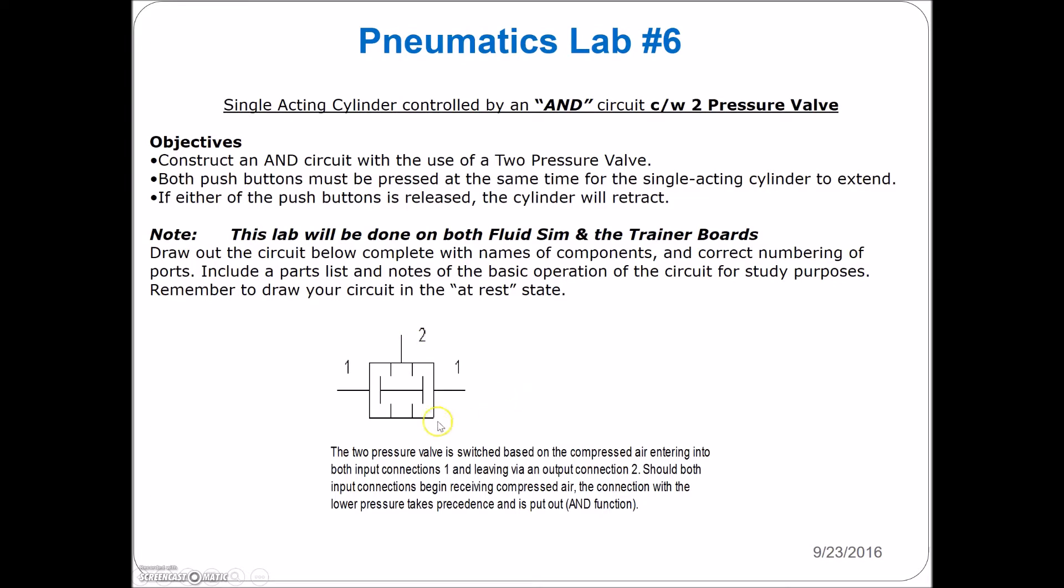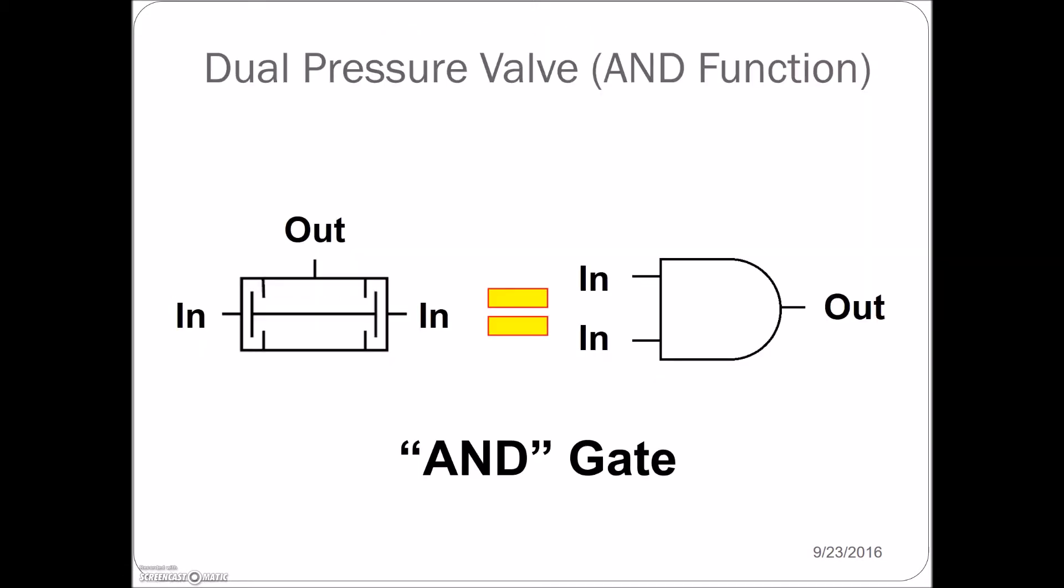The way that you'll distinguish which one this is in the lab is embossed on the front—it'll have this exact image of the AND valve. The other name for this is the two-pressure valve, which needs two pressures of basically equal value before the output will actually happen. Pushing both push buttons at the same time will allow the single-acting cylinder to extend. If either push button is released, the cylinder will retract. Basically, this symbol corresponds to our AND gate.